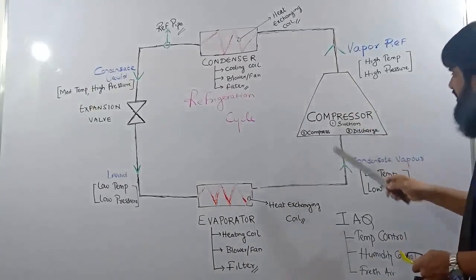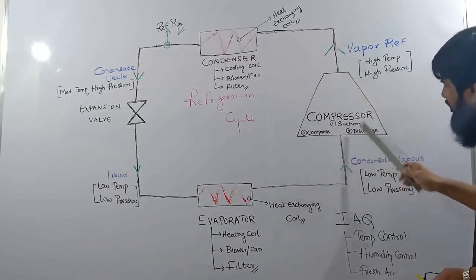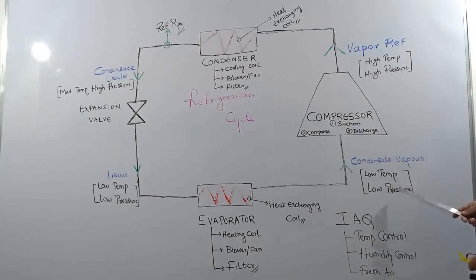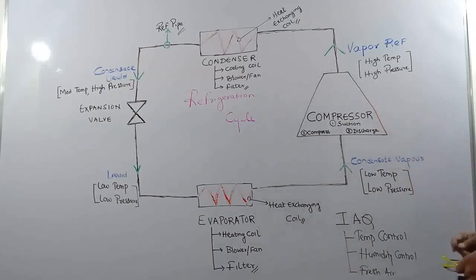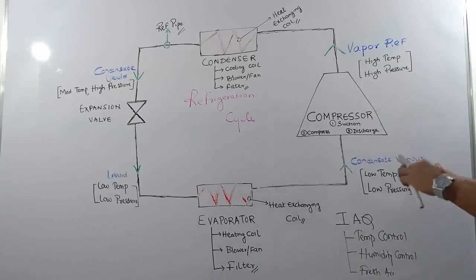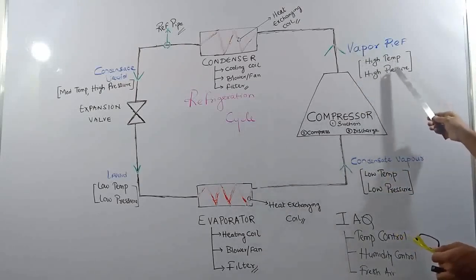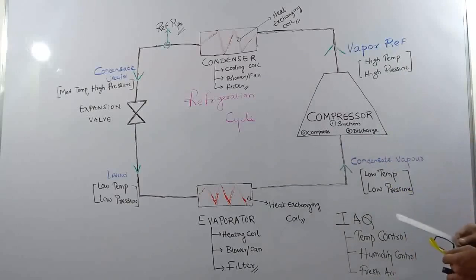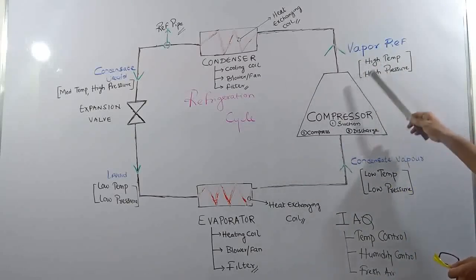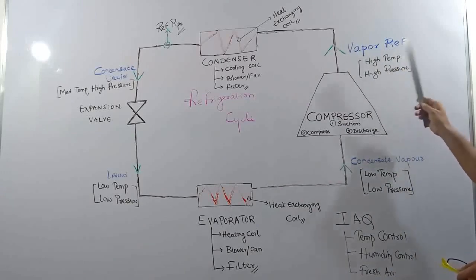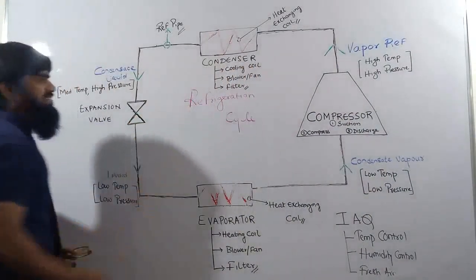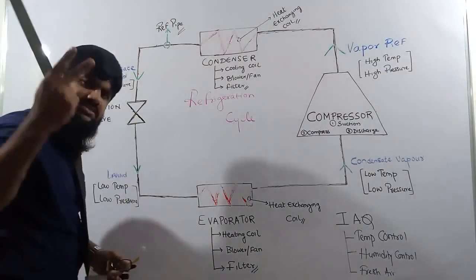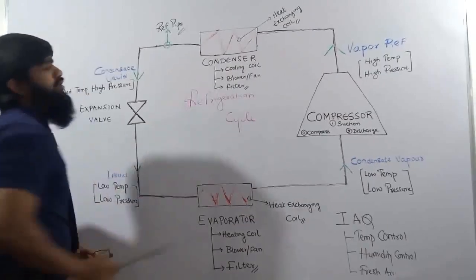At the inlet of the compressor, we get superheated vapor at low temperature and low pressure. This vapor is compressed by the compressor. As the gas is compressed, its temperature and pressure both increase. At the output of the compressor, we get a high temperature, high pressure vapor refrigerant. This is then given to a set of cooling coils which we call the condenser. The condenser can be air-cooled or water-cooled.